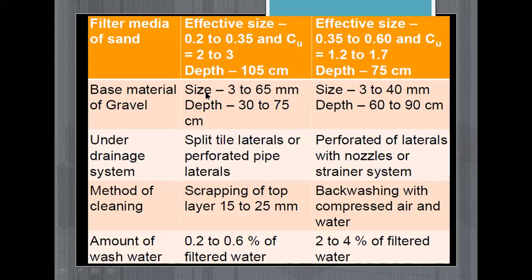Gravel is used as a base material in both cases. The size of the gravels in the slow sand filter is 3 to 65 mm and the depth of gravel is 30 to 75 cm. In the rapid sand filter the size of the gravels is 3 to 40 mm, and the depth of gravels is 60 cm to 90 cm.